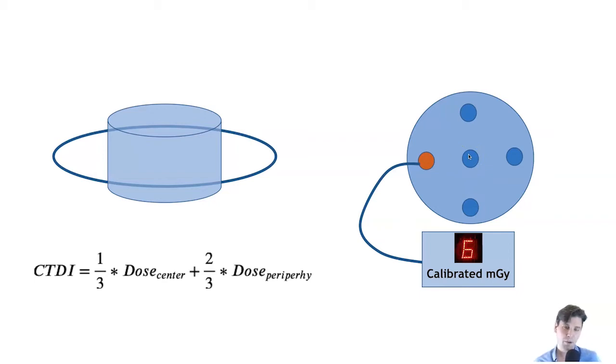And then there's a bunch of different methodologies that, for the most part, as a technologist, you don't really have to be concerned with: the difference between the CTDI, the CTDI FDA, the CTDI 100. The different methodologies are necessary because the scanners have wider and wider collimations now. So the methodology had to be updated for calculating the CTDI. But in general, the CTDI is the absorbed dose for the system for that phantom size.